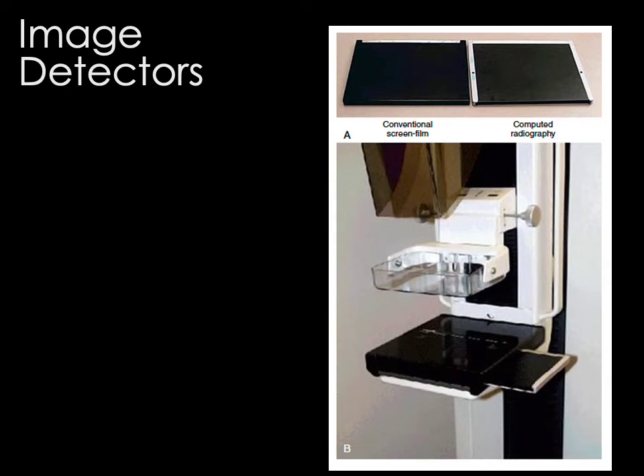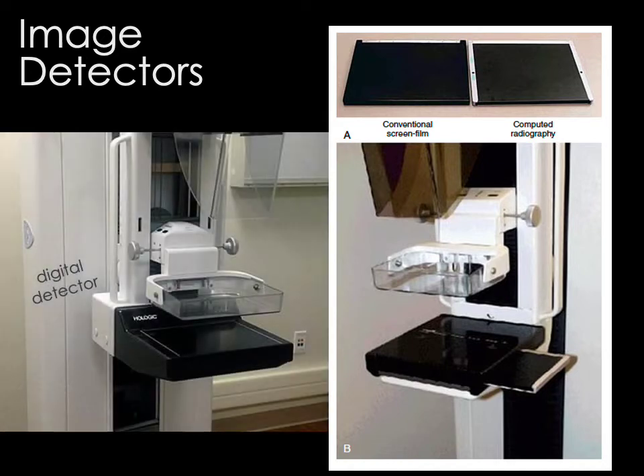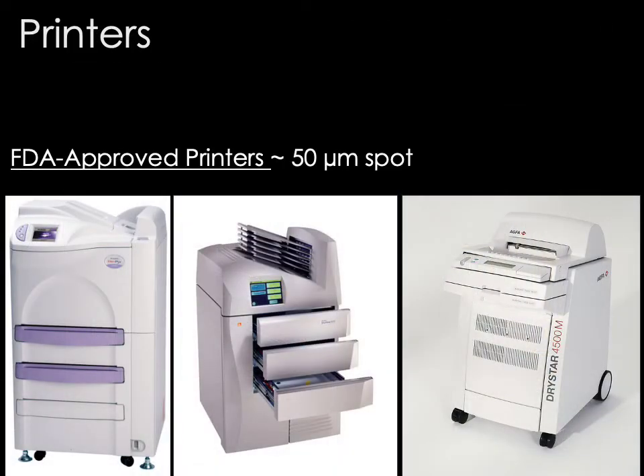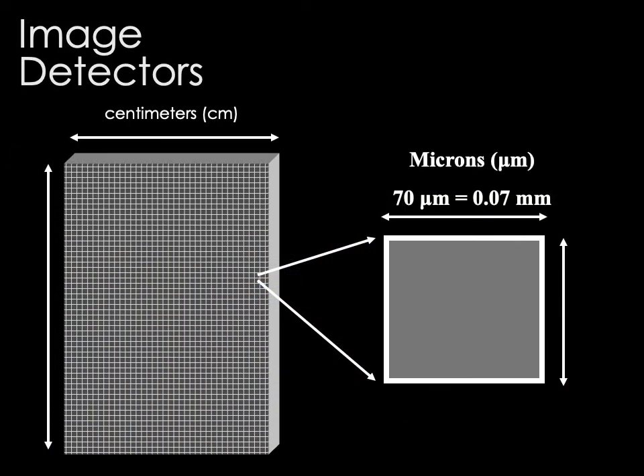As for the image detector, a CR cassette or film can be slid into the side of the breast support, but these days most mammography detectors are digital. Mammography also has specialized printers that allow mammograms to be printed onto film at high resolutions of about 50 microns, though the FDA requirement for facilities to have printing capability has gone away. Because of the need for high spatial resolution, digital detectors used in mammography typically have a pixel size of 70 microns — about half the size used in digital detectors for general radiography.